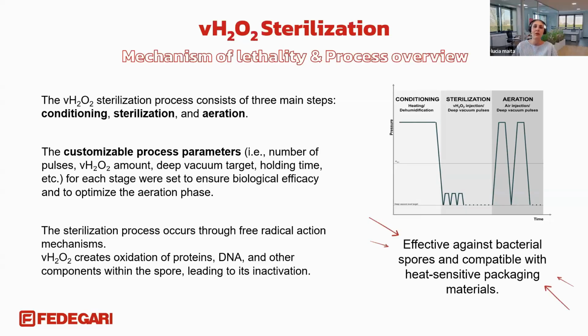During the conditioning, the load is heated and the humidity is reduced in order to ensure consistent process conditions. Conditioning is followed by the sterilization phase, where the air is removed and hydrogen peroxide is distributed into the chamber in one or more pulses. The load is exposed for a defined holding time. The sporicidal effect of hydrogen peroxide is based on oxidative damage to the cellular components, leading to microorganism inactivation.